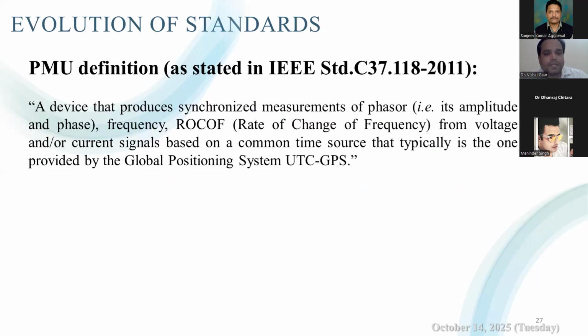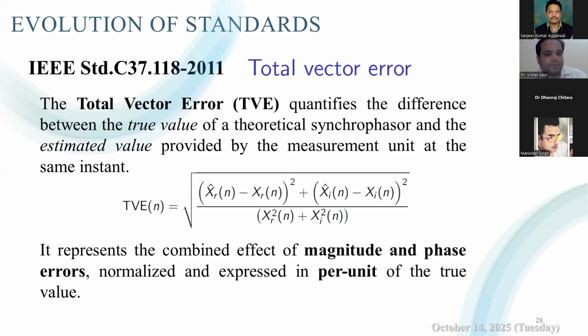According to this particular standard C37.118, the PMU is defined as a device that produces synchronized measurements of phasor, its amplitude and phase, frequency, and rate of change of frequency from voltage and or current signals based on a common time source that is typically provided by the GPS, global positioning system.